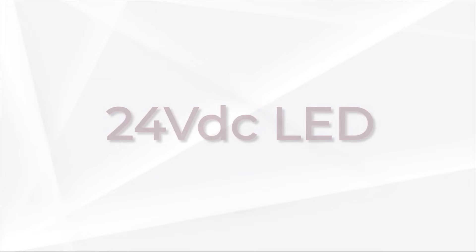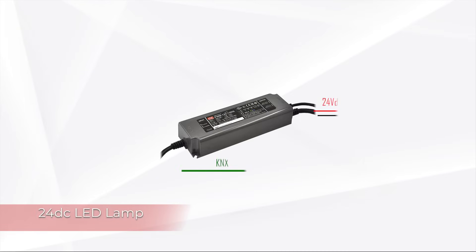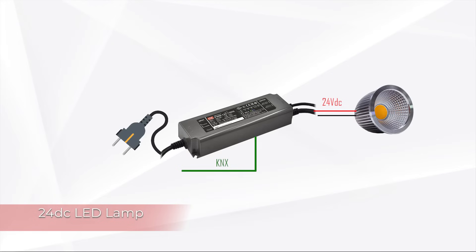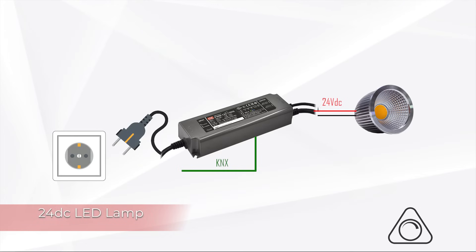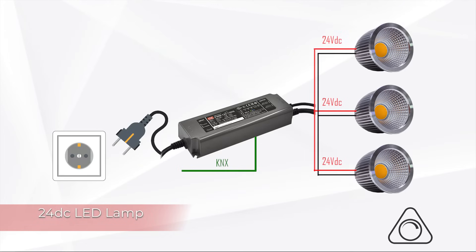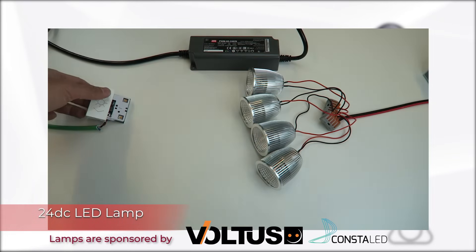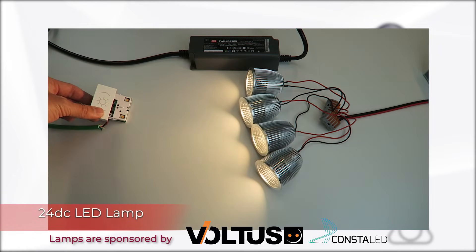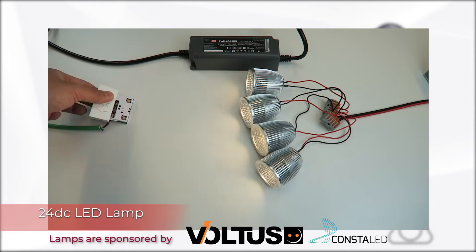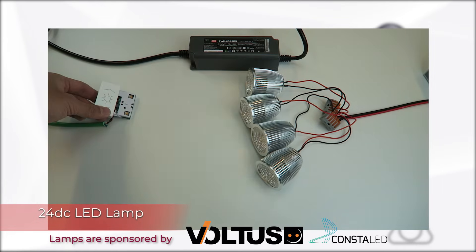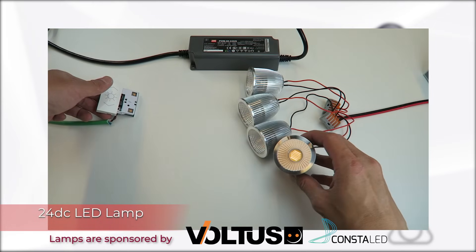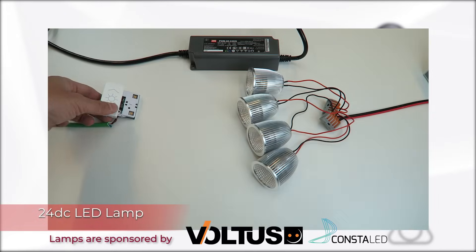The third application is to drive 24 volts DC LED lamps for spot lighting as well. The benefits are similar to the 12 volts AC described previously; additionally, the driving voltage of 24 volts results in smaller electrical losses along the cable. You can use a 24 volts LED driver for on, off, and dimming functions, with multiple lamps in parallel. In the demonstration, the light turns on then off, then on again with a long push to start dimming. It uses a 60 watt driver for several 24 volt LED lamps in parallel, with the minimal output set to 0.01% for applications where low luminescence is needed.